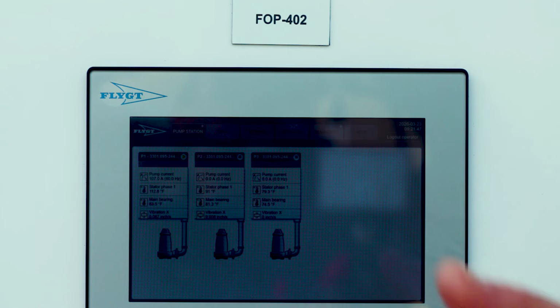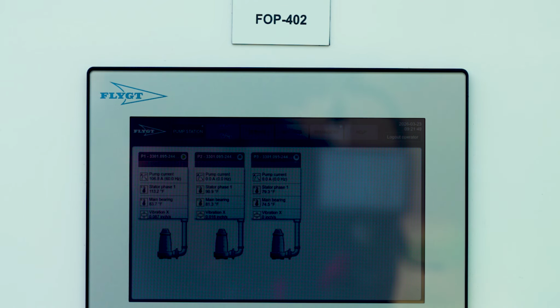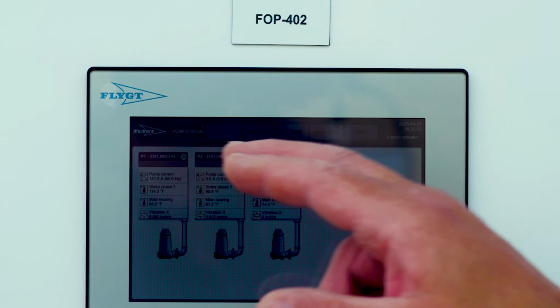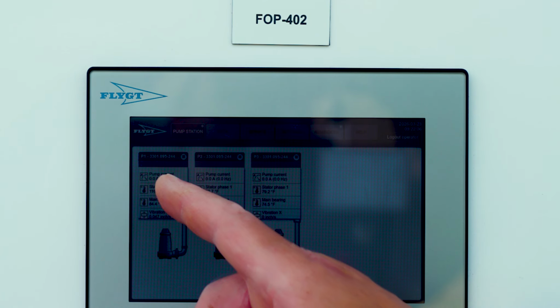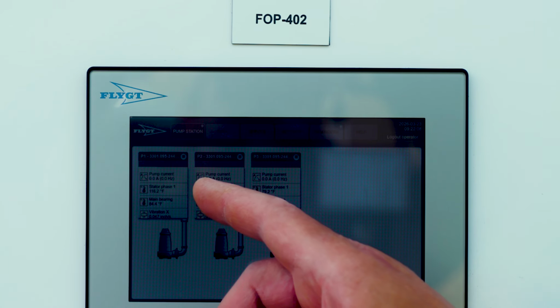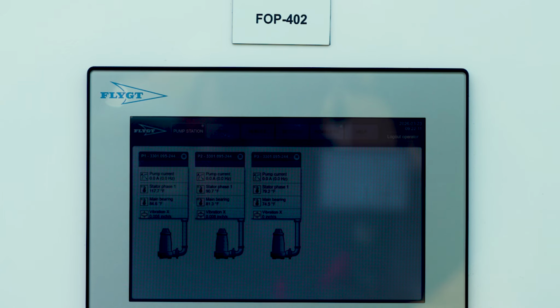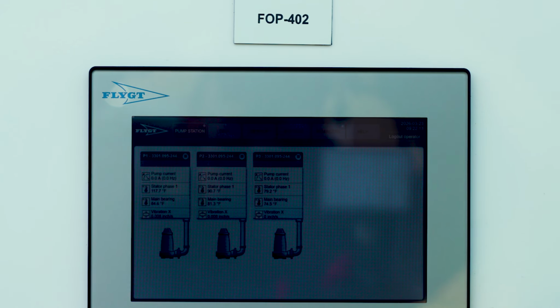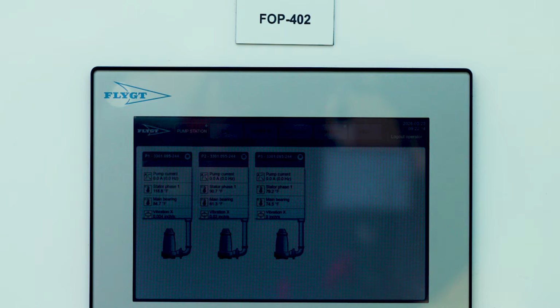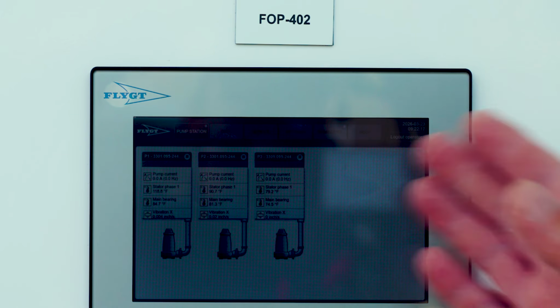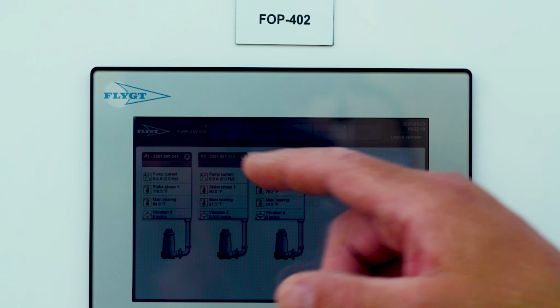So as these run, we'll get trends for them, and we'll adjust alarm levels according to how they run. But that's not something we're going to show you in this class. That's something we do as a maintenance item when we come do our annual inspections. On the main screen, all the pumps display their current, stator temperature, main bearing, and vibration. And as long as all those are normal, you won't have any alarm, but you'll get used to seeing what they normally run at, and they should run fairly close to each other.